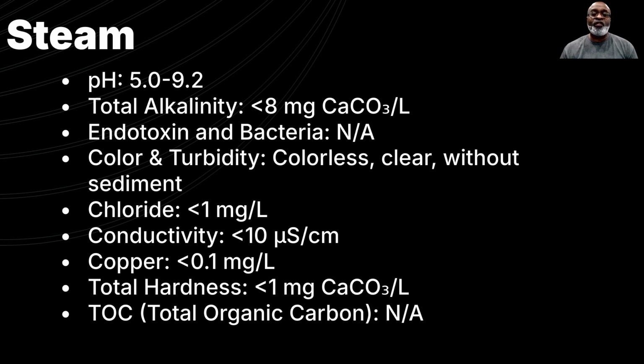Endotoxin, not applicable for steam. Color and turbidity must be colorless, clear, and free of sediment to prevent visible impurities. Chloride, less than 1 milligram per liter to protect equipment from corrosion. Conductivity must not exceed 10 microsiemens per centimeter, ensuring low ionic content. Copper, restricted to less than 0.1 milligrams per liter to avoid contamination.